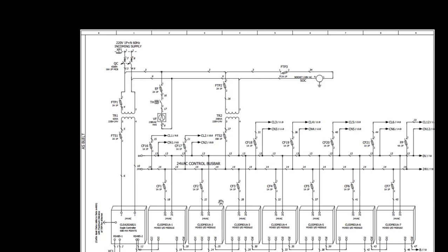It is very important to understand this wiring, because sometimes a module may not be turned on and there is no power in that module, so you have to go back to the drawing and know where the problem is. And then you will see on each cable there is a number. This is a cable number, so you will find this number inside the panel. For example, this cable is number 3. The cable coming out of CF1 is number 18, so this number 18 cable is going to the module, so you can trace it back to the fuse from the module.